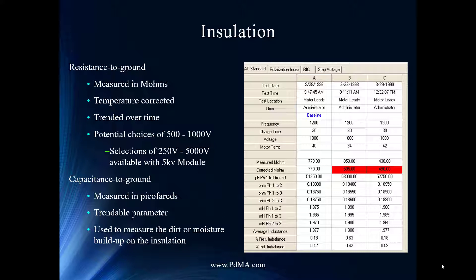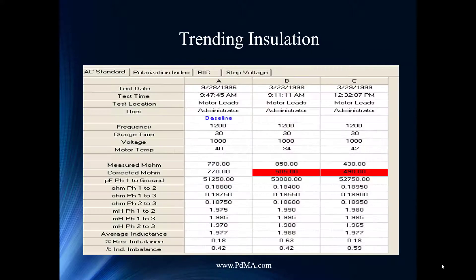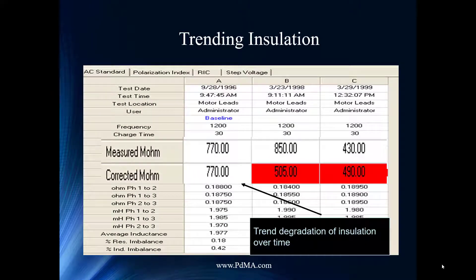Capacitance to ground also verifies good grounding connections. If during the test you see an over-range where the capacitance signal is unable to measure a value, it becomes important to inspect your ground — whether the motor is grounded to the building bus or the facility earth ground. If the motor is not properly grounded through the casing, it becomes a fire hazard or shock hazard to the end user.